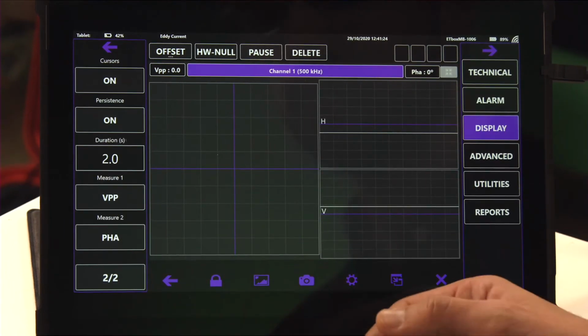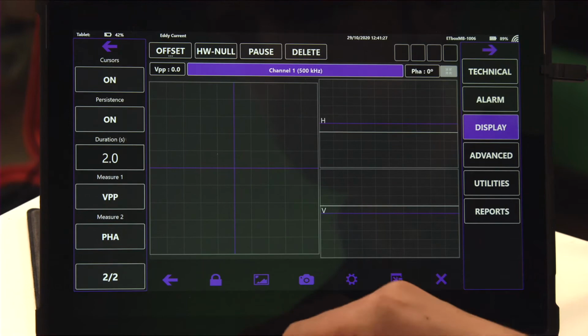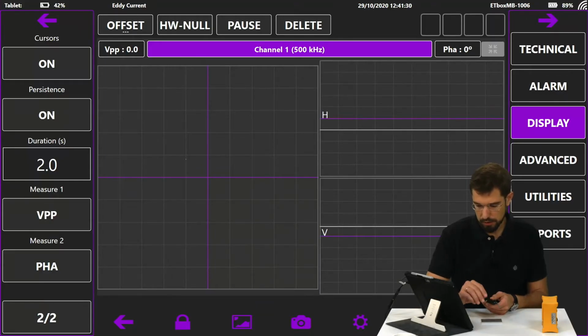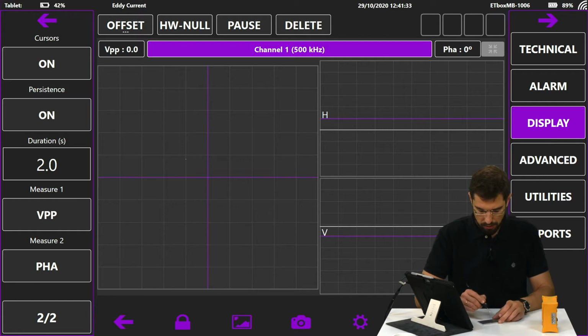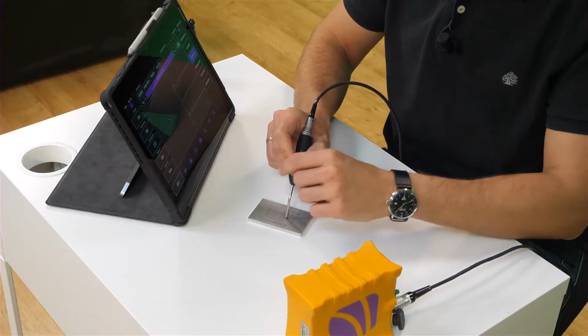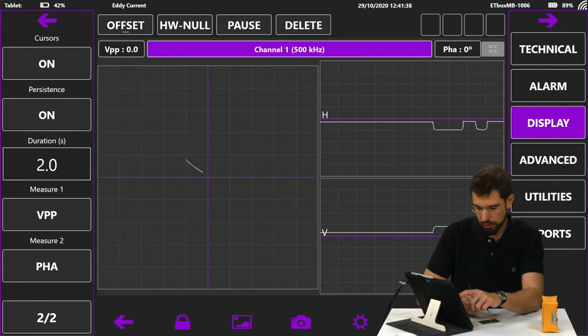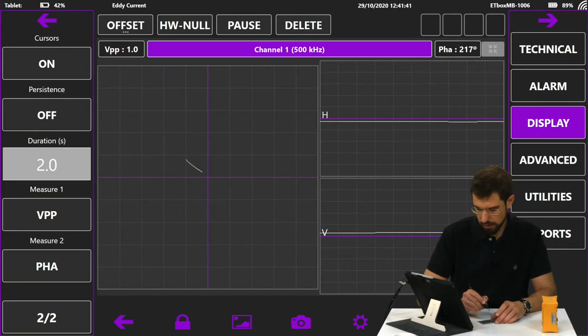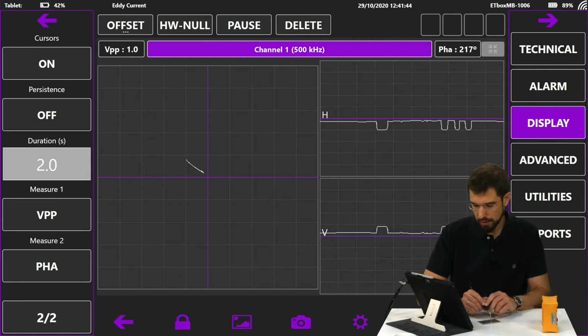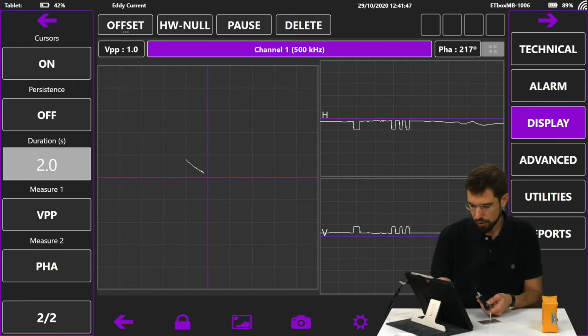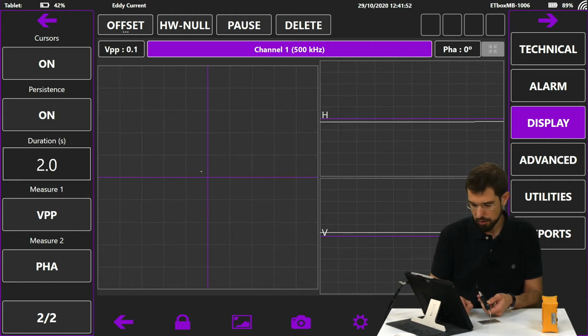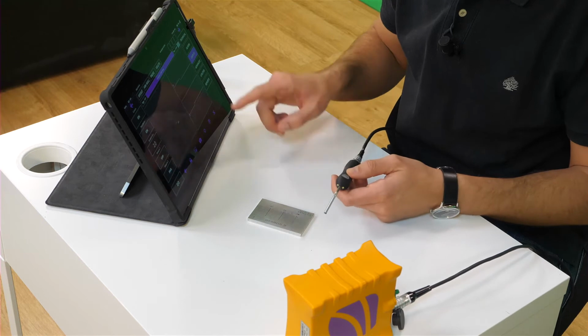Once we have that part configured, we can also see there are several other options among which we can choose. The equipment is acquiring, and it's important to take into account that we can turn the persistence mode on or we can turn the persistence mode off. That way, we see that if it's turned off, the whole signal that's acquiring until the buffer is full accumulates on the screen. However, if we turn it on, what we see is that it only represents the 2 seconds that we have configured. We're going to leave it that way to work.